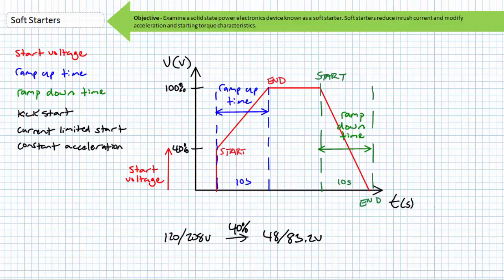Constant acceleration mode necessitates feedback from a tachometer, which if you'll remember from the mechanical power, torque, and speed lecture available at the Big Bad Tech channel, is a means of measuring rotational speed. The rotational speed transducer updates the soft starter with the speed of the rotor, and the soft starter can back off or step on the gas for the ramping voltage accordingly to keep acceleration inside a given range. This closed-loop control feature allows the soft starter to govern the physical output of a motor. Note this feature borders the traditional boundary between soft starters and motor drives.